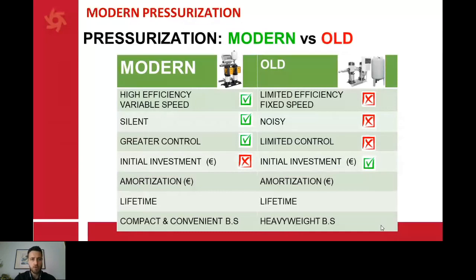But the amortization is much greater in a modern one, because the cost of the purchase in a modern one is the least important part in the life cycle of a booster set. And the old one, you have to maintain it, you have to pay all the electrical costs and maintenance. At the end of the life cycle of the pump, the old system is much more expensive overall than a modern system. The lifetime is also longer in a modern one, because the pumps suffer much less, since the pump is always working on the demand of the installation. And what about the volume? The modern ones are compact and convenient booster sets, while the old ones are heavyweight booster sets, and you don't need that special tank that is so big.